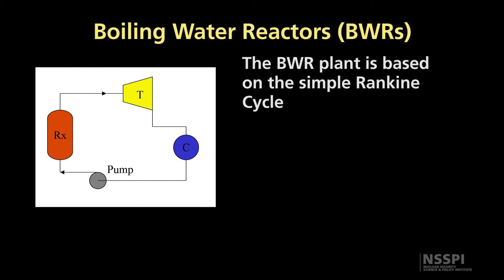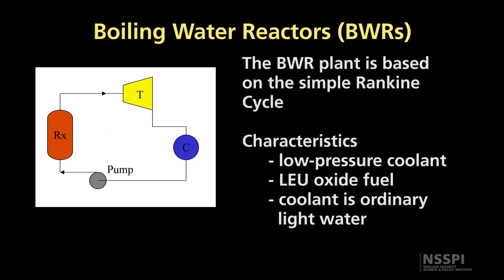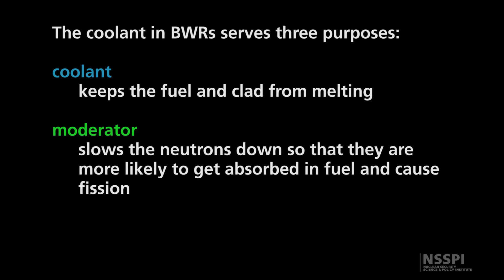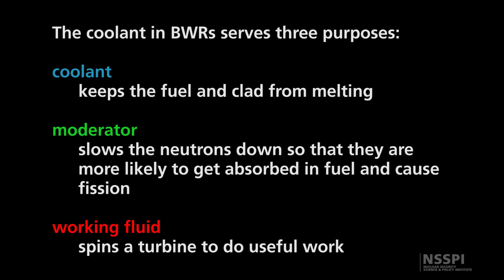The BWR, or boiling water reactor, is a very simple reactor type. The reactor produces steam, that steam drives a turbine, the steam then gets condensed in a condenser and pumped back through the reactor. The thermodynamic loop for it is very simple. This reactor operates off of a low pressure light water coolant and uses a low enriched uranium oxide fuel. The coolant itself serves three purposes: it cools the fuel and cladding so the fuel doesn't melt; it acts as the moderator that slows neutrons down so they can cause fission; and it is the working fluid that spins the turbine and produces electricity.